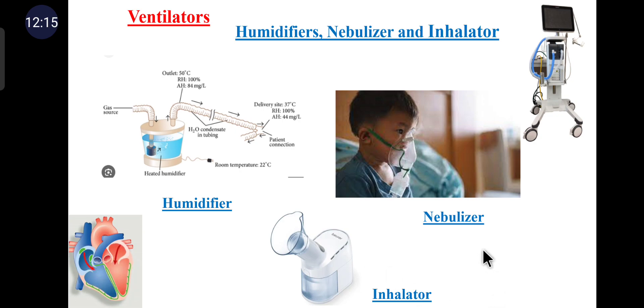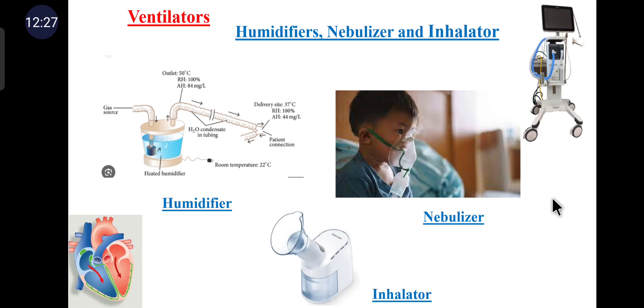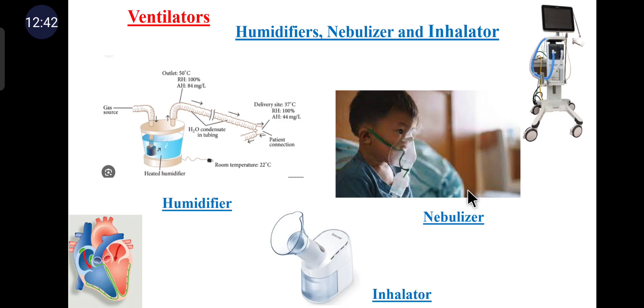A nebulizer is used when water or some type of medication suspended in the inspired air as an aerosol is to be administered to the patient. The water or medication is picked up by a high-velocity jet of air and made to impact against one or more baffles, breaking the substance into controlled-size droplets which are then applied to the patient via the respirator. More efficient nebulizers are based on high-intensity ultrasound energy which vibrates the substance to produce a high volume of minute particles.